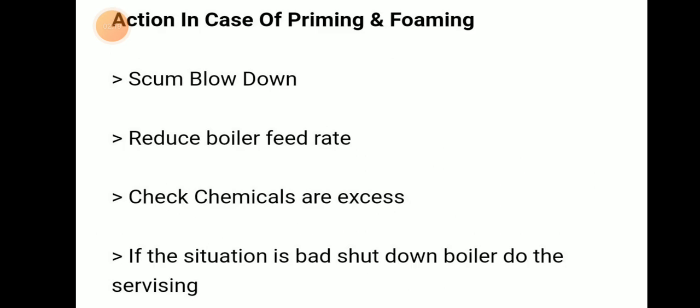In case of priming and foaming, the actions to take are: perform scum blowdown, reduce boiler feed rate, and check boiler water treatment to see if chemicals are in excess. If the situation is bad or out of control, shut down the boiler for servicing.